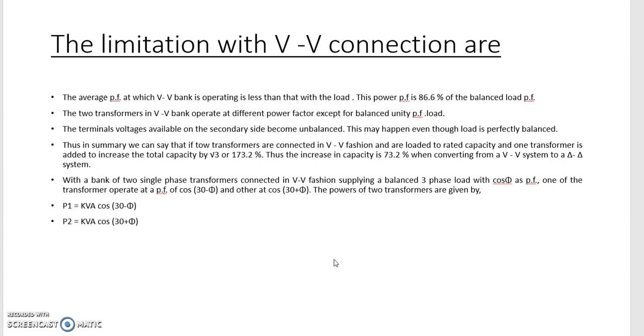There are certain limitations of this kind of connection. The average power factor at which V-V bank is operating is less than with the load. This power factor is 86.6 percent of balanced load power factor. The two transformers in V-V bank operate at different power factor except for balanced unity power factor load. The terminal voltage available in the secondary side becomes unbalanced. This may happen even though load is perfectly balanced.